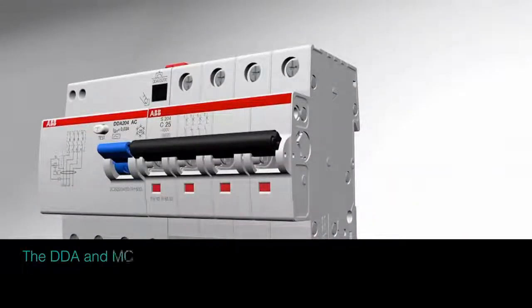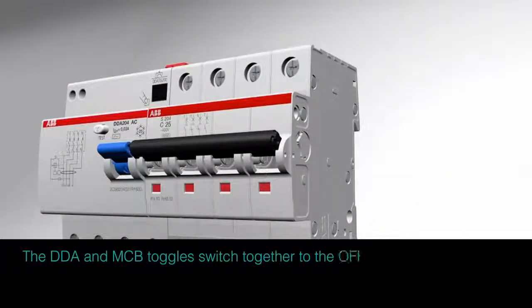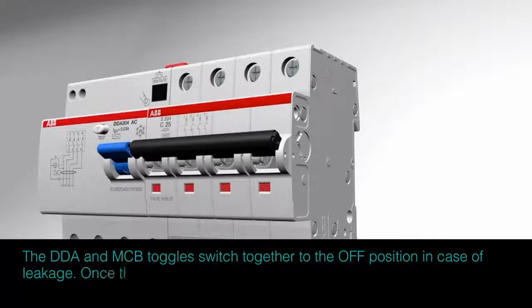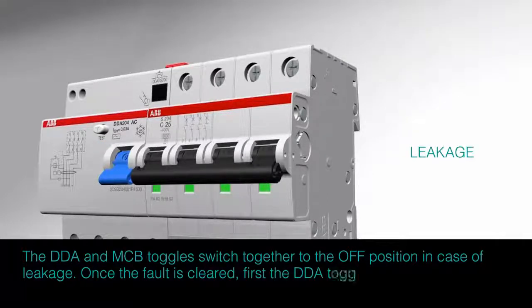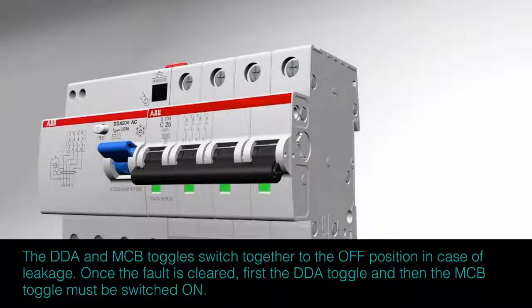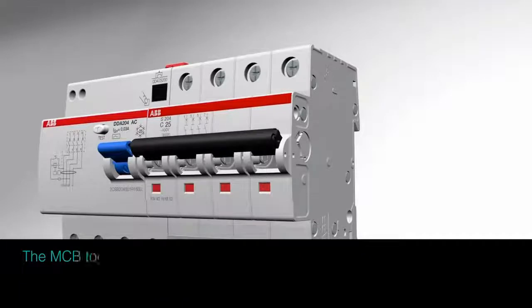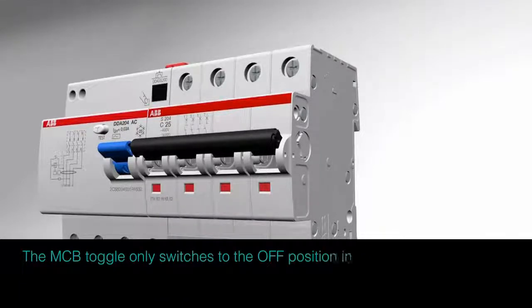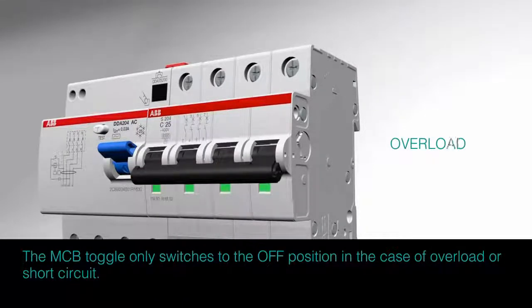The DDA and MCB toggles switch together to the off position in case of leakage. Once the fault is cleared, first the DDA toggle and then the MCB toggle must be switched on. The MCB toggle only switches to the off position in the case of overload or short circuit.